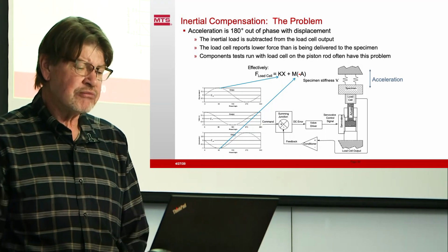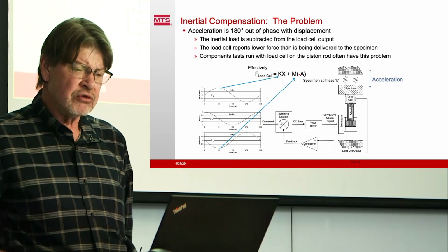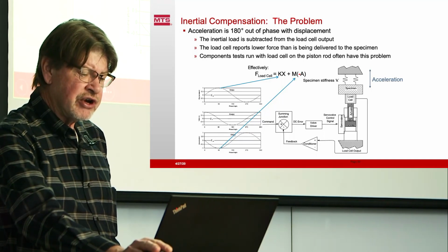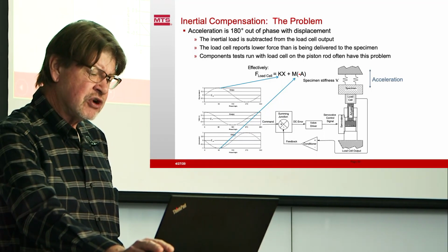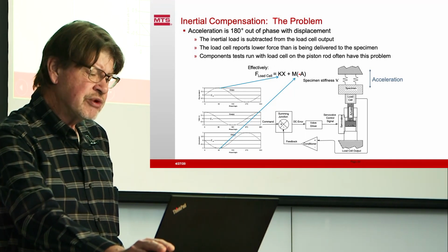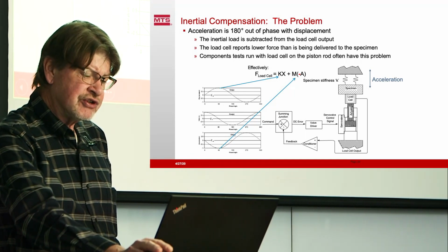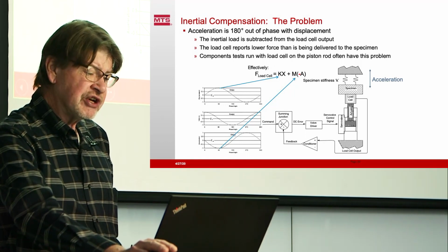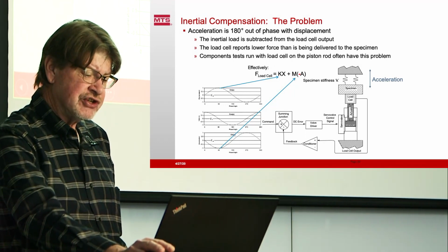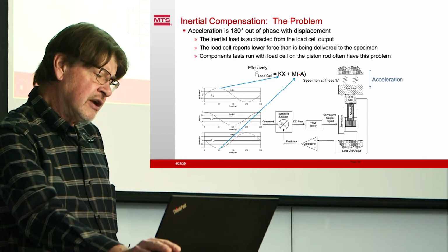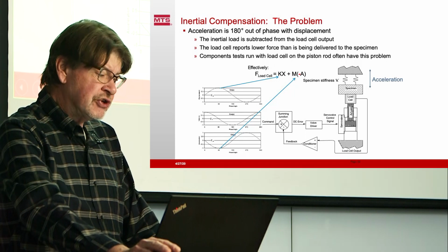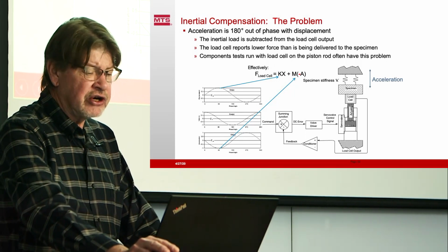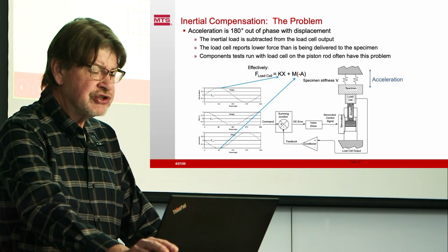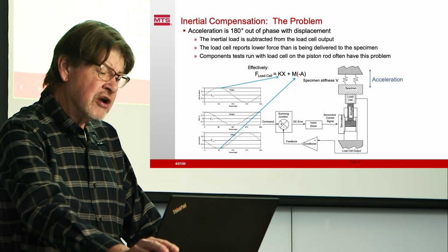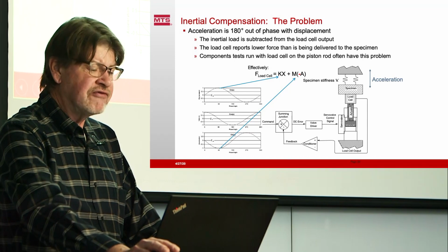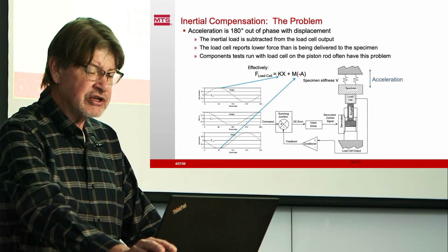Well, what we've got is moving masses and a remote load measurement. So with our load transducer down here, we've got the mass of the specimen and fixtures, and somewhere up here is where we really want the load. As we move, we not only compress the spring that's our specimen, but we also accelerate, and therefore the mass that's here sees an acceleration force. Now, the way Newton taught us calculus, displacement and acceleration are essentially 180 degrees out of phase. So really what the load cell does is subtract the inertial load from the spring load and report lower force out of the load cell than the specimen actually sees.